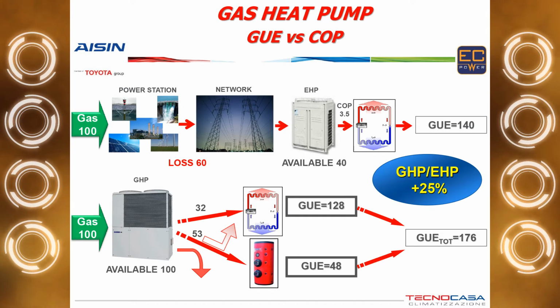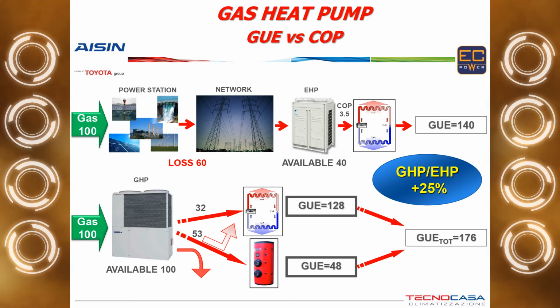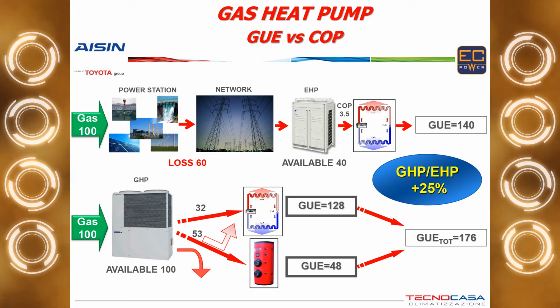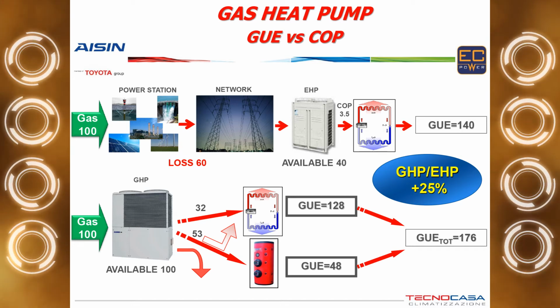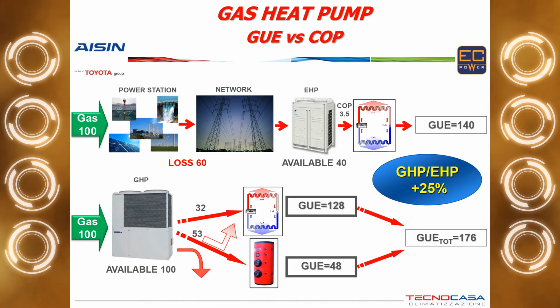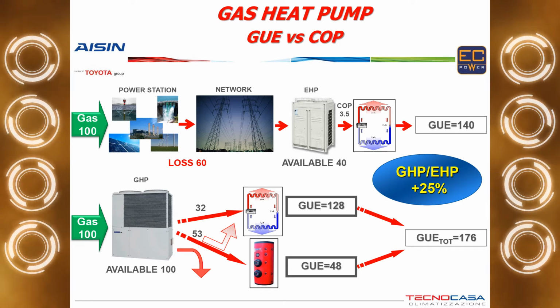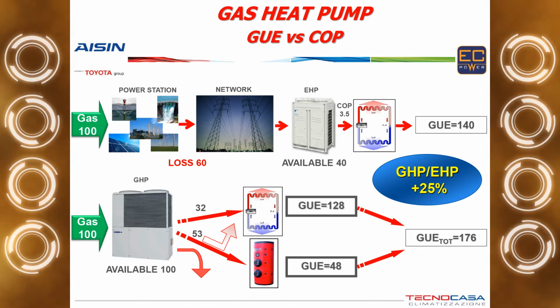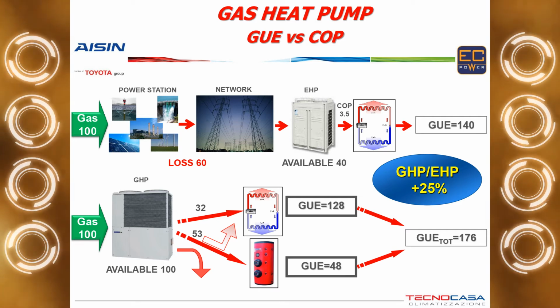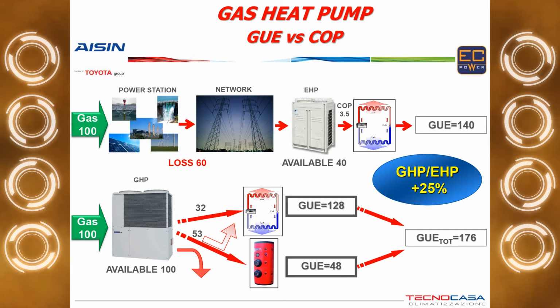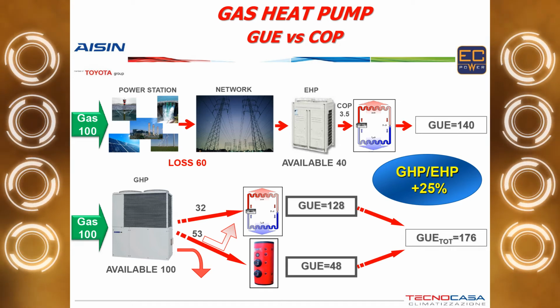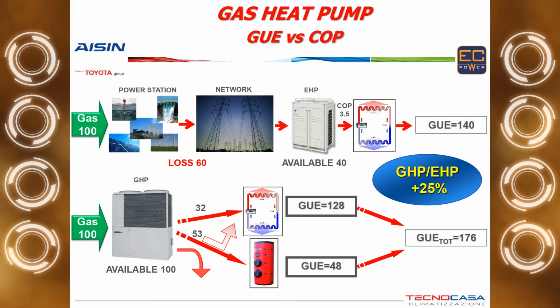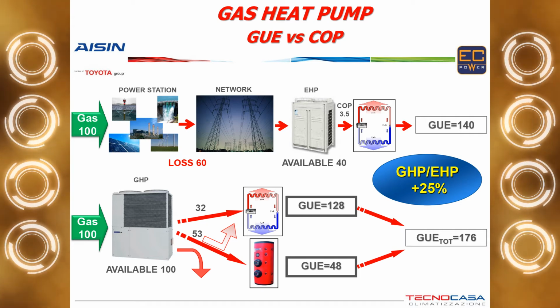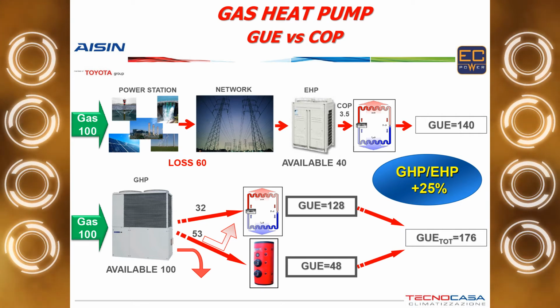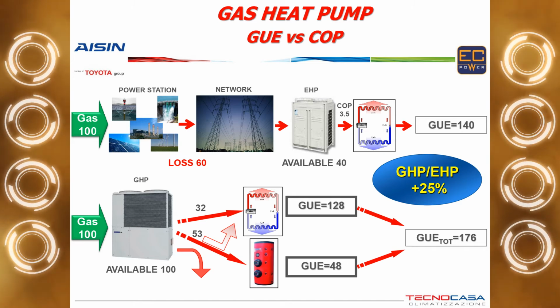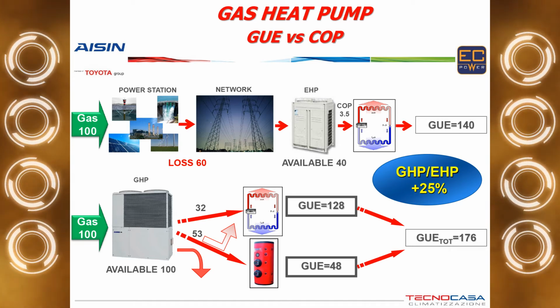When we speak about the gas-driven heat pump, so far we don't speak about COP, but we speak about GUE, which is the gas utilization efficiency. So when we compare the performances of a gas-driven heat pump with the performances of an electric chiller, we can see that figures don't match. We are used to hear that electric heat pump COP in winter or in summer, EER in that case, is about 4 or higher, depending on the size. Well, you can see from our documents that the gas-driven heat pump has a GUE of maximum 1.6, 1.7. So if you compare 4 with 1.7, there is no comparison. It's better this one because it's 4.